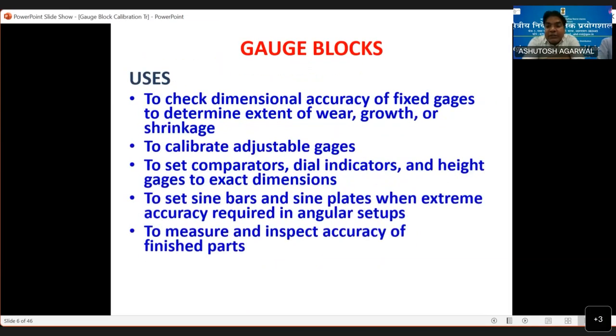So what are the uses? To check the dimensional accuracy of fixed gauges, to determine the extent of wear, growth or shrinkage. So you check every year whether your gauge is 100 or not. If you use a gauge for 10 years, you will definitely know that after 1 or 2 years it will have some shrinkage. I will tell you why it is shrinkage, because this steel gauge is made of carbon and iron, so carbon gets precipitated. I will tell you later.